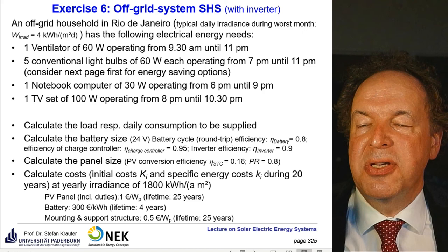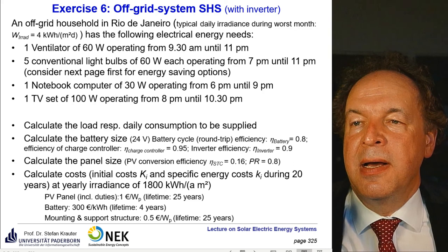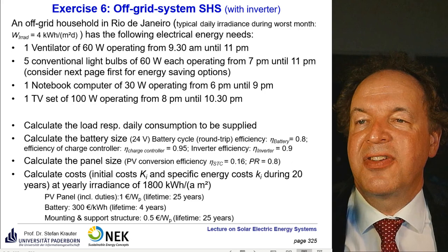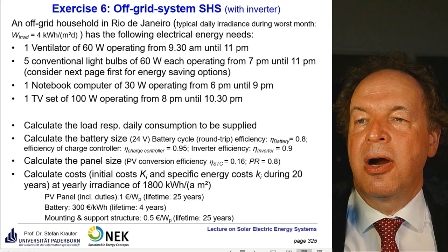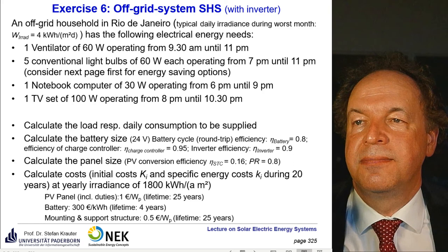For the battery, due to the high ambient temperature, the lifetime is not very long. So we consider a lifetime of 4 years. And the cost of such a battery is 300 euro per kilowatt hour. The mounting and support structure costs are 0.5 euro per watt peak, also with a lifetime of 25 years.